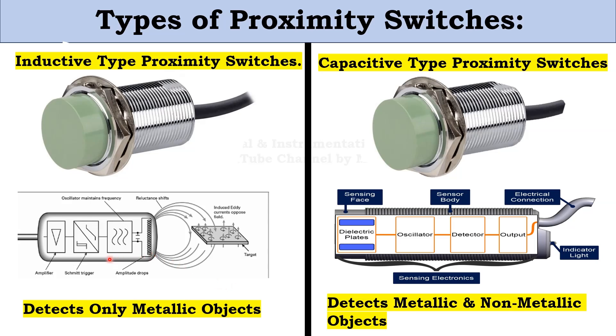Let's understand the working principle of the Inductive Proximity Switch. Once power supply is received, an oscillator gives signal to a coil inside the switch. This coil produces an electromagnetic field around it. When any metal comes near the coil, the current flowing in the coil changes. This change is detected by the sensor, which gives output to the PLC indicating that a metal is detected.